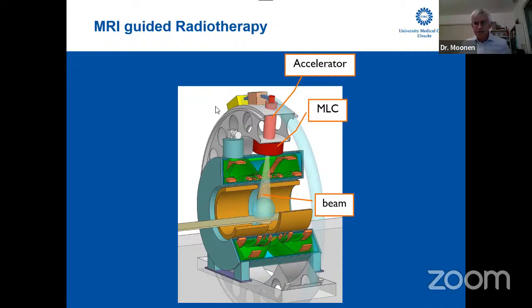You can see here the accelerator on this large metallic structure, and it's firing through the MR system. Here you see the patient lying on the table in the MR system. Overall, this MR is almost a standard 1.5 Tesla MR system. It is a bit special in the sense that the design of the primary coils is done in such a way that there is zero magnetic field in this rotating large metallic structure. And that's of course needed because otherwise you would have a change in magnetic field all the time. If this is perfectly zero, then there is no effect upon a rotating metallic structure.